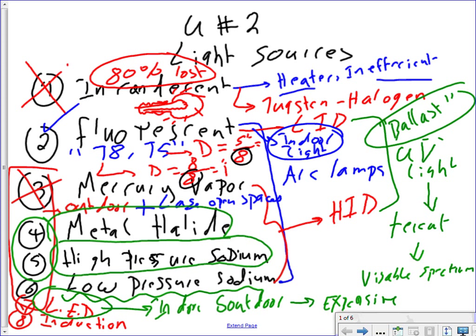If you look at the lumen maintenance curve on the right side, after 24,000 hours these lamps will maintain only up to 40% of their lumens. There are a couple of concepts for the lamps. Number one, how long will this lamp live is a big deal: 24,000 hours, or 10,000 hours, or 1,000 hours. Number two, how much of the lumens will be maintained over the life of the lamp? That's a major part. Will it maintain 50% of it after 24,000 hours?